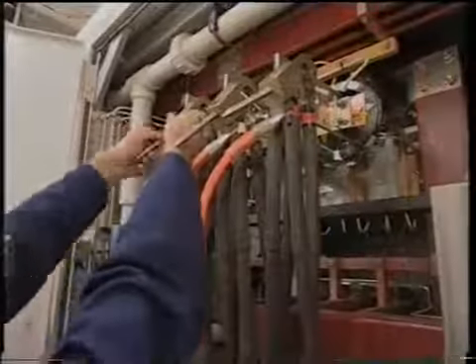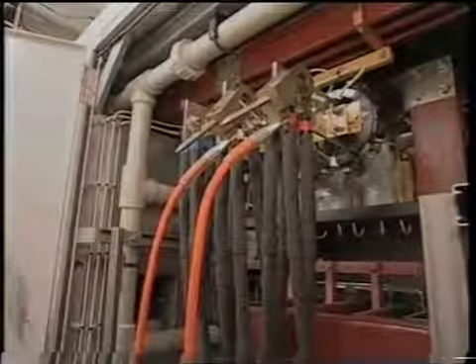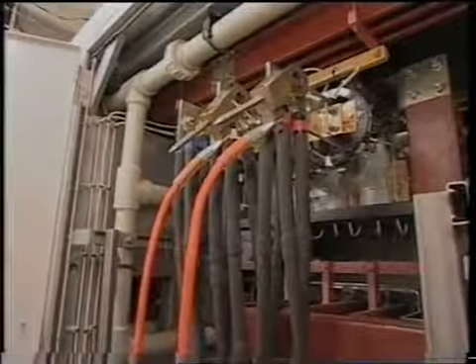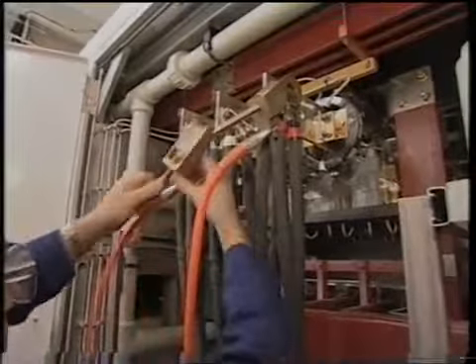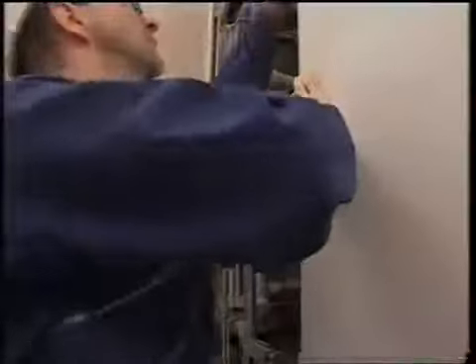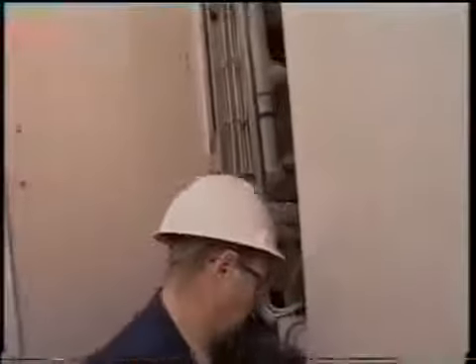After all tests and other maintenance tasks are completed, as listed on the permit to work, the additional earth leads are removed, first from the phases and then from the local earth point. The panel doors are closed and locked and the warning signs removed. The circuit breaker tags will also be removed and the locks returned to the lockout box.